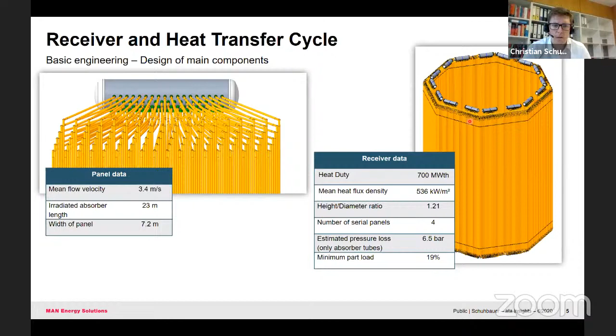We have 4 serial panels in a row. The salt flow velocity through the panels is 3.4 meters per second. So this results in the pressure loss, if you only look on the absorber tubes, of 6.5 bar. We reach a minimum part load of 20%. And the panel width is around about 7.2 meters. And for transport, we have divided them. So this is the reason that you see here 2 headers.